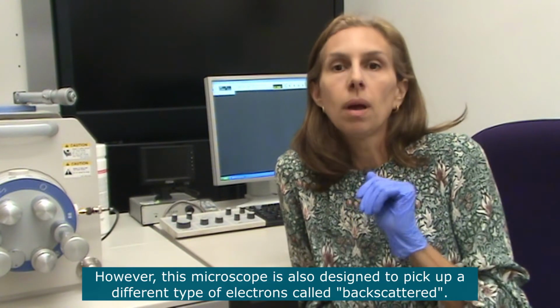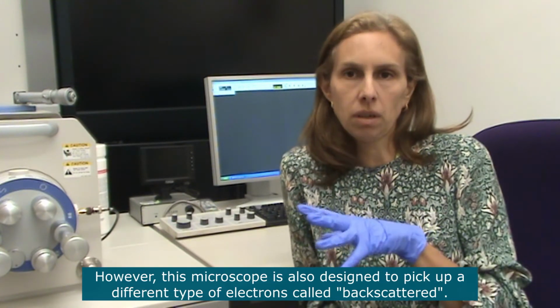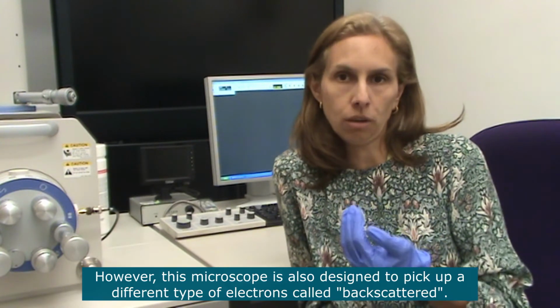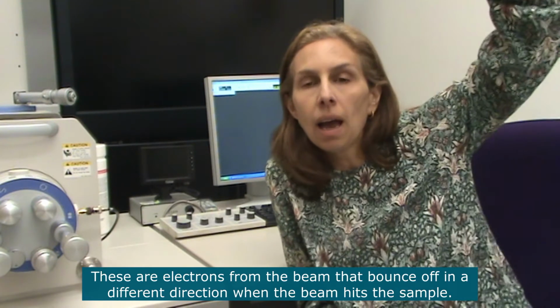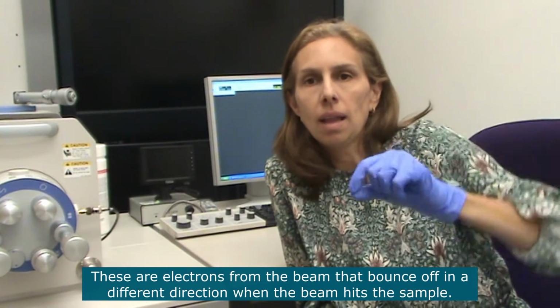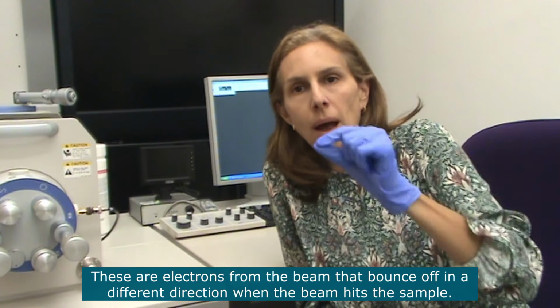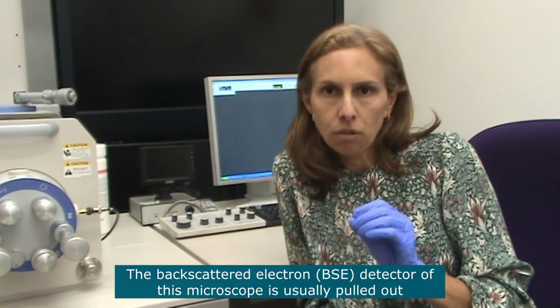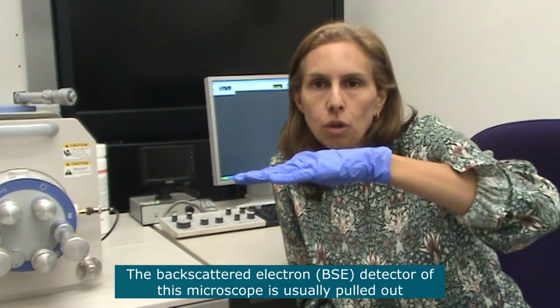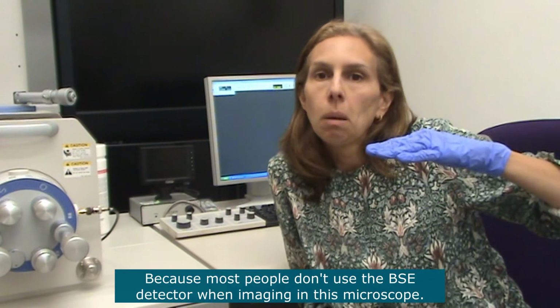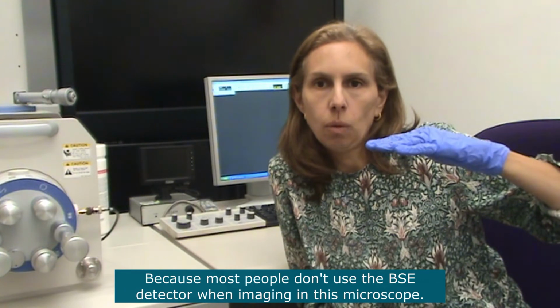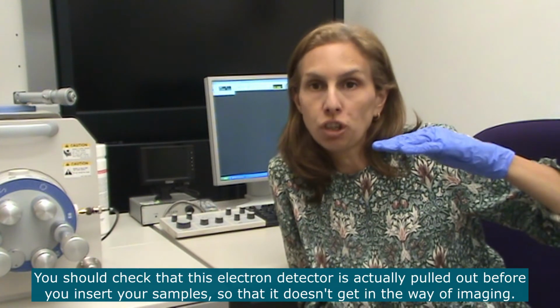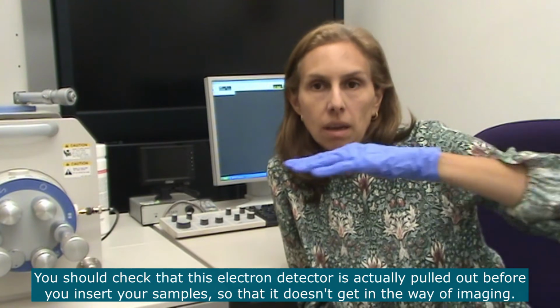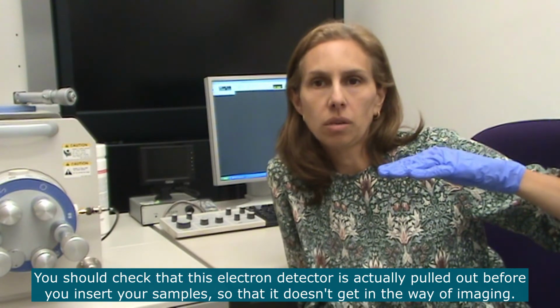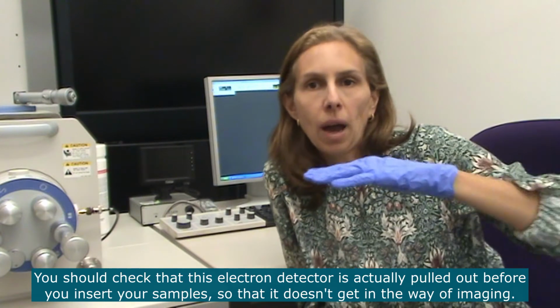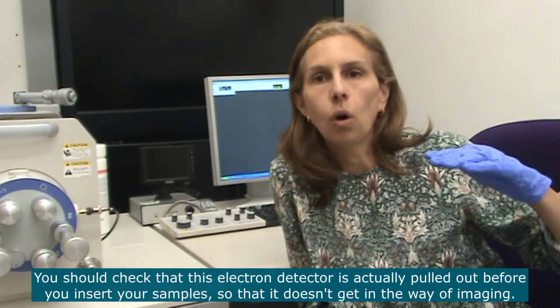However, this microscope is also designed to pick up a different type of electrons called backscattered electrons. These ones are actually electrons from the beam that when the beam hits the sample, they bounce off. The backscattered electron detector of this microscope is usually pulled out because most people don't use backscattered electrons when they image in this microscope. However, you should check that this electron detector is actually pulled out before you insert your sample, because it can get in the way of you actually imaging if it's been inserted and not retracted.